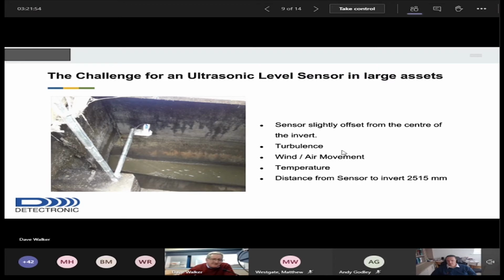Turbulence, as I mentioned. Now, you can overcome that turbulence if you've got all that energy coming back to the ultrasonic sensor. So what you need to do there is mount the ultrasonic sensor much closer to the target of measurement, and that will give all that energy coming back and not be affected as much by turbulence of the actual flow itself. The limitation on that, I'll touch on in a bit, is because there's a deadband on an ultrasonic sensor, and the rate of rise could actually go into the deadband.